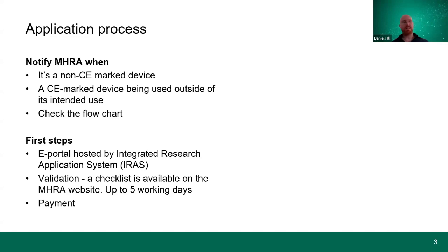And that includes things, depending on the type of the device, like software. We need a full software development plan and documentation set to the standard 62304, I think it's IEC 62304. We need all of that to make sure that the software has appropriate safeguards in place and risk management in place if it's going to be driving or controlling or involved in this medical device in some way.